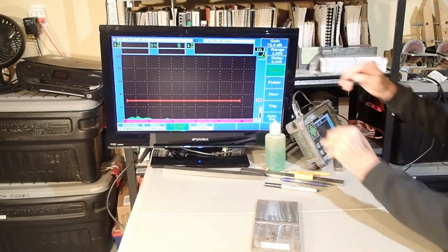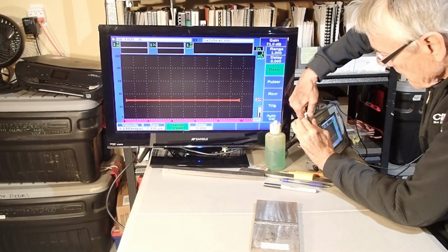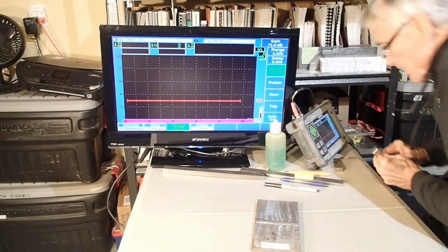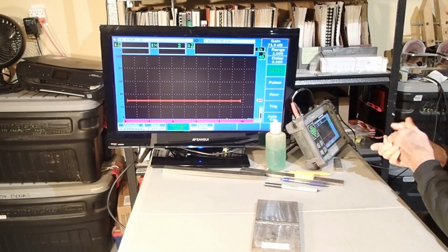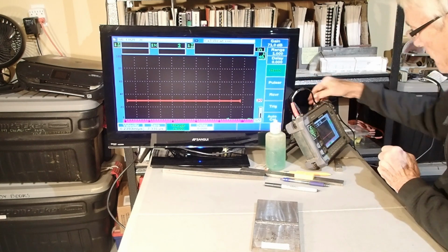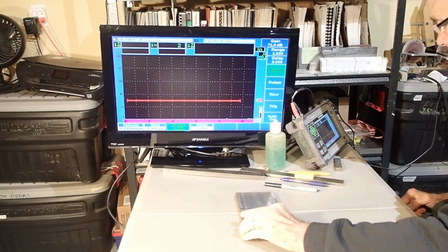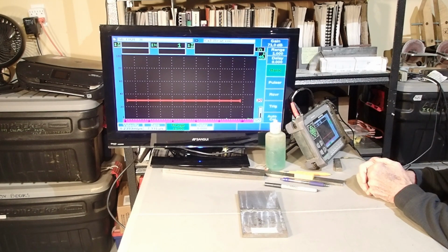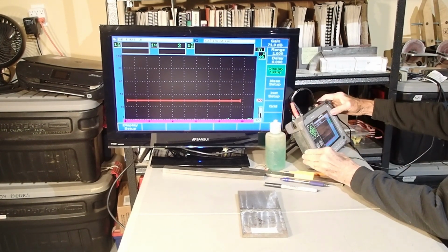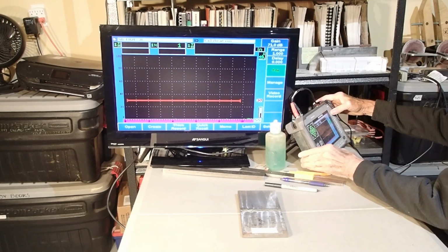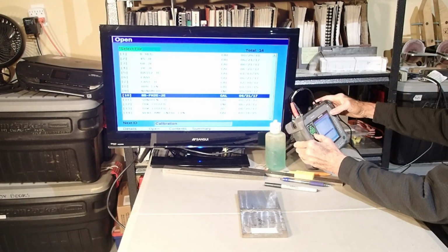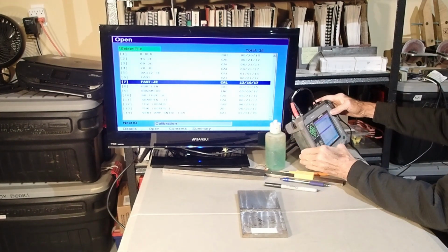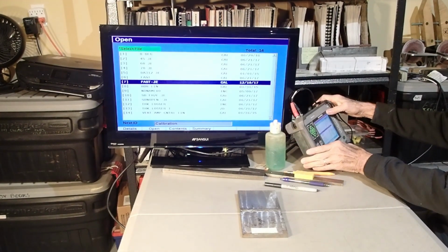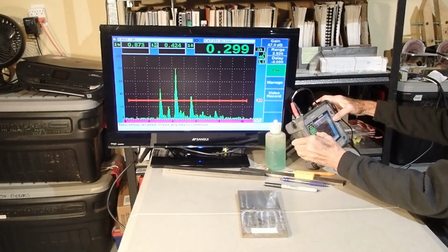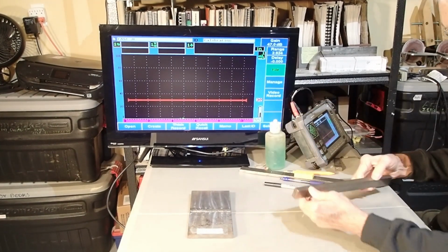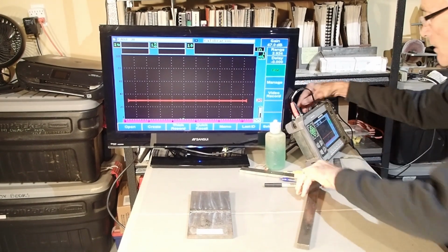Alright, let's see what a fast scan would look like of this. So we've got our fast, it's actually a Sonotest Q-Scan 1 probe, but it's a fast type probe, an angled all-way probe for thin-walled material. So let's recall that cal. So that's what I have in here as my fast JE probe. Open, open, open. Contents recall. And we recall the cal, let's check the cal.